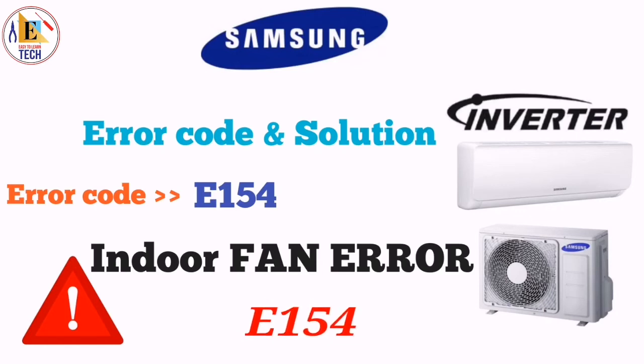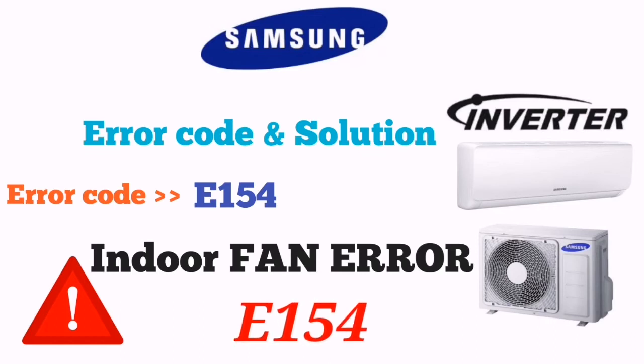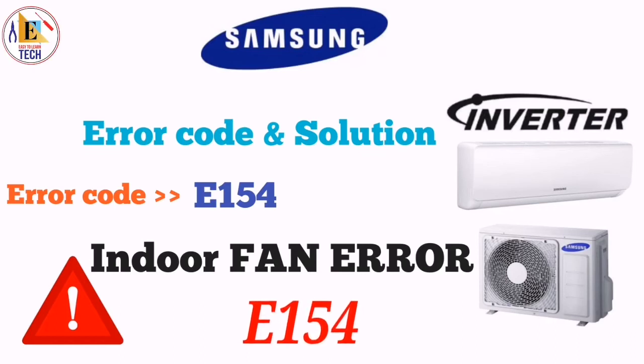If the voltage is okay, then it's good, our PCB is not faulty. If the voltage is not good, then we have to replace our PCB. If the voltage is good, it means our fan motor is faulty, and we have to replace our fan motor.